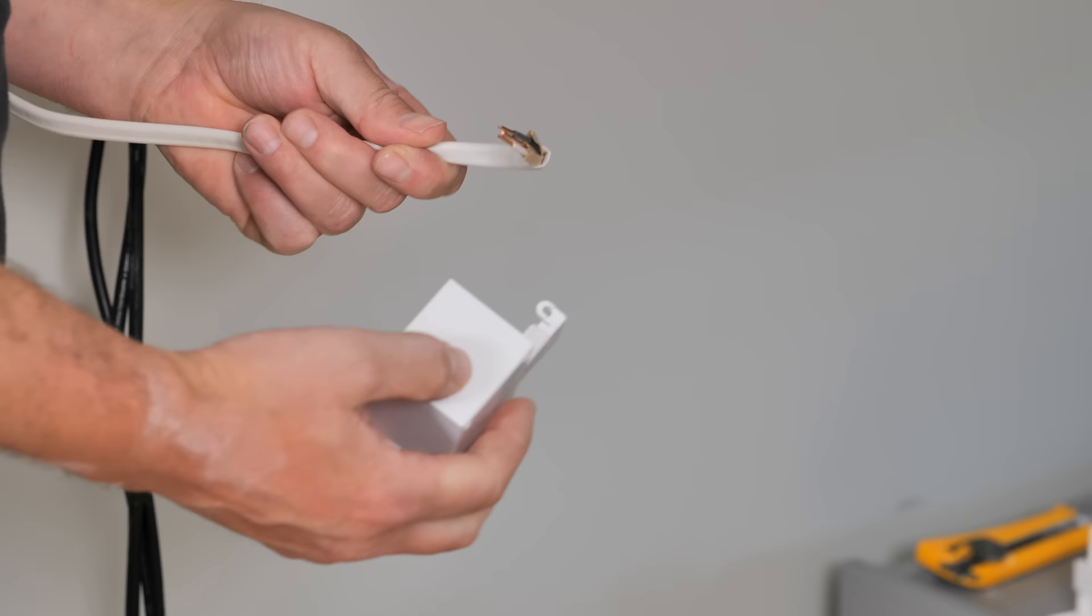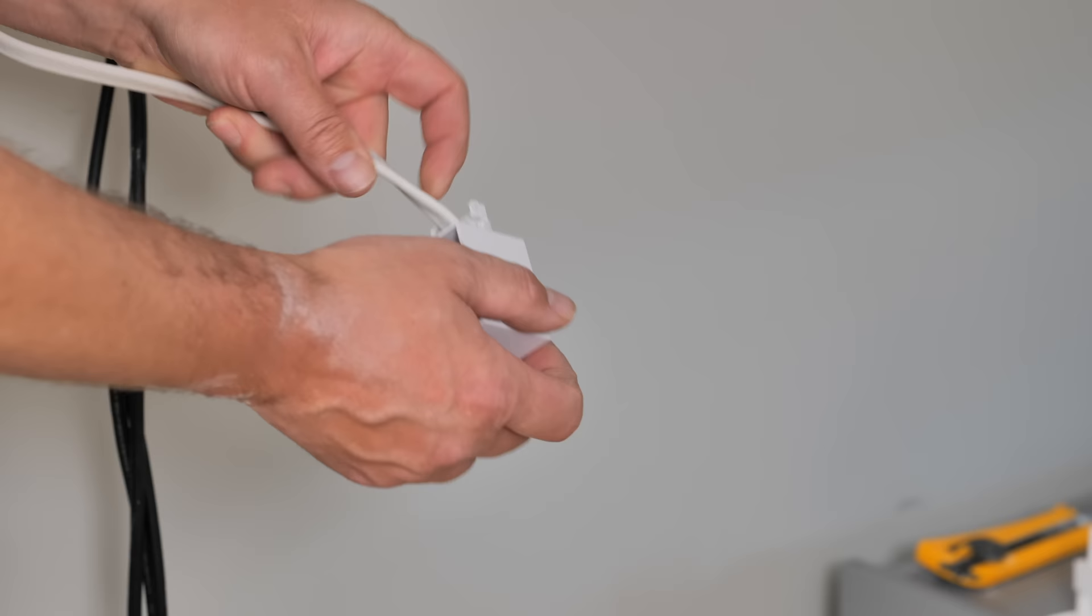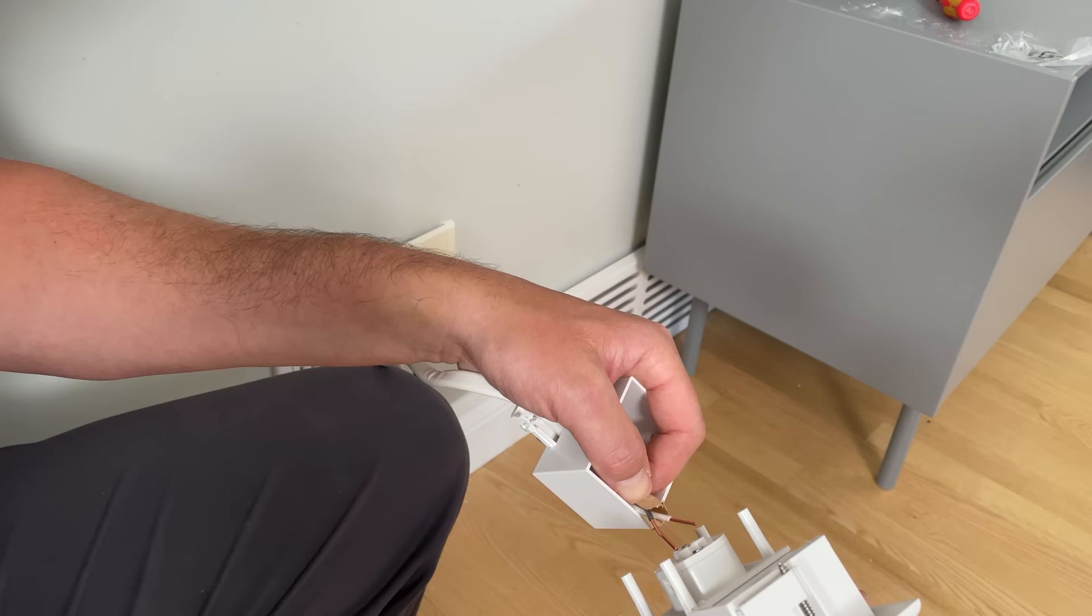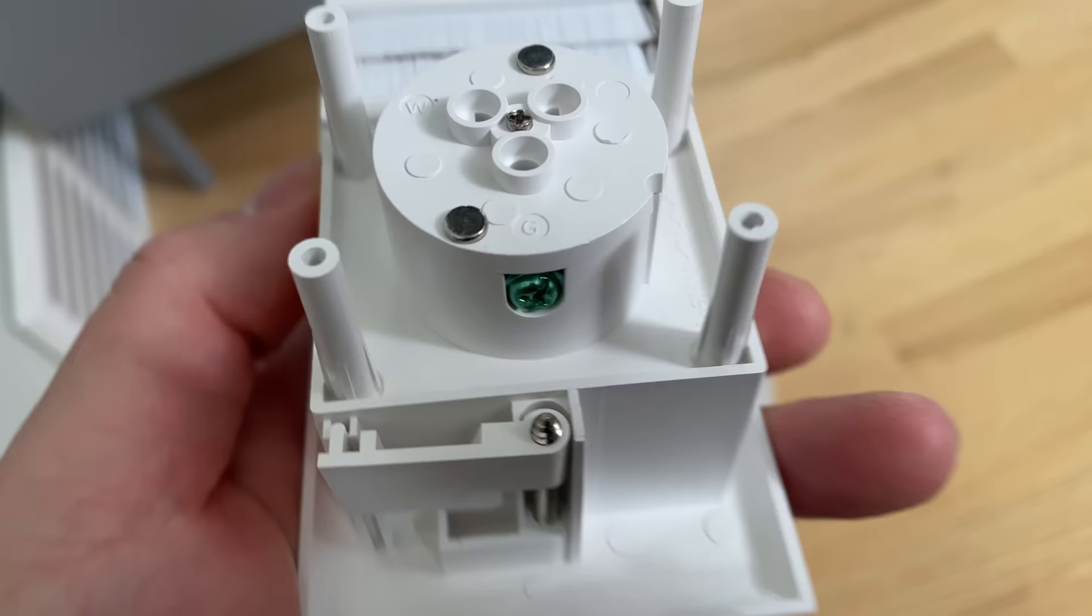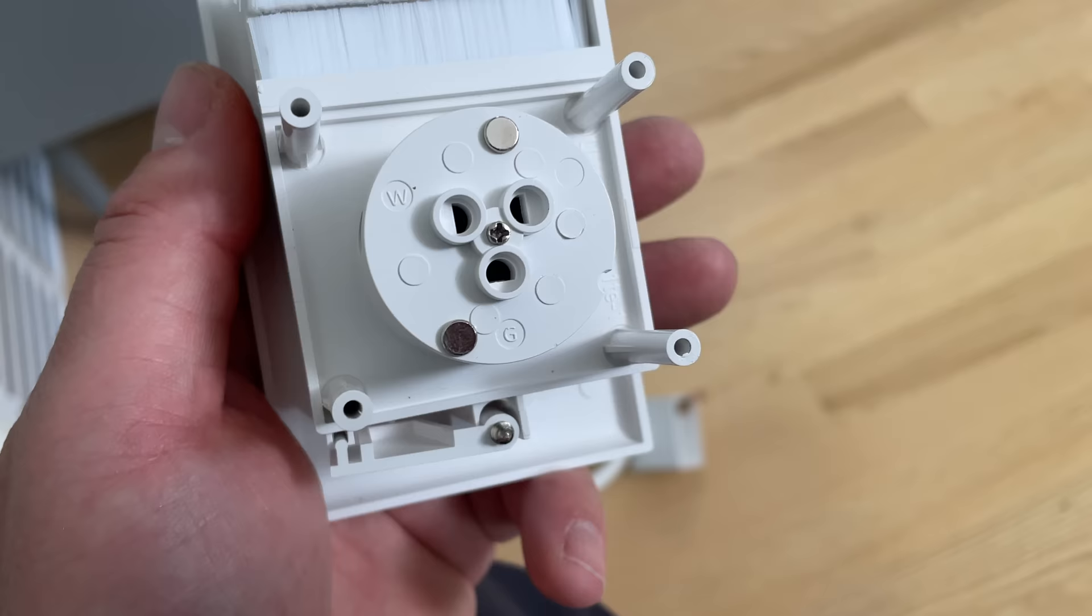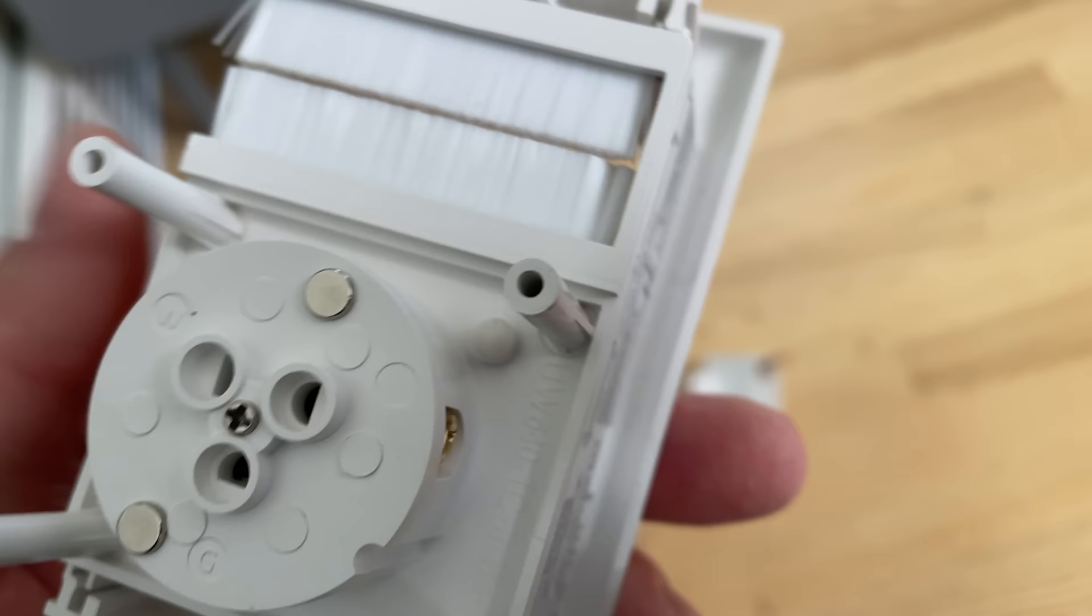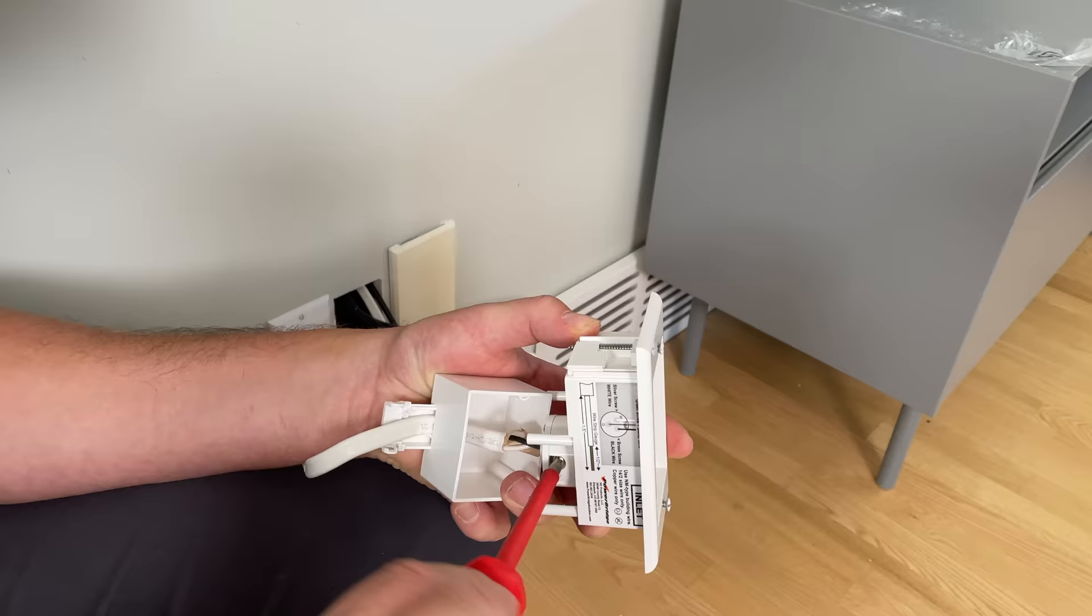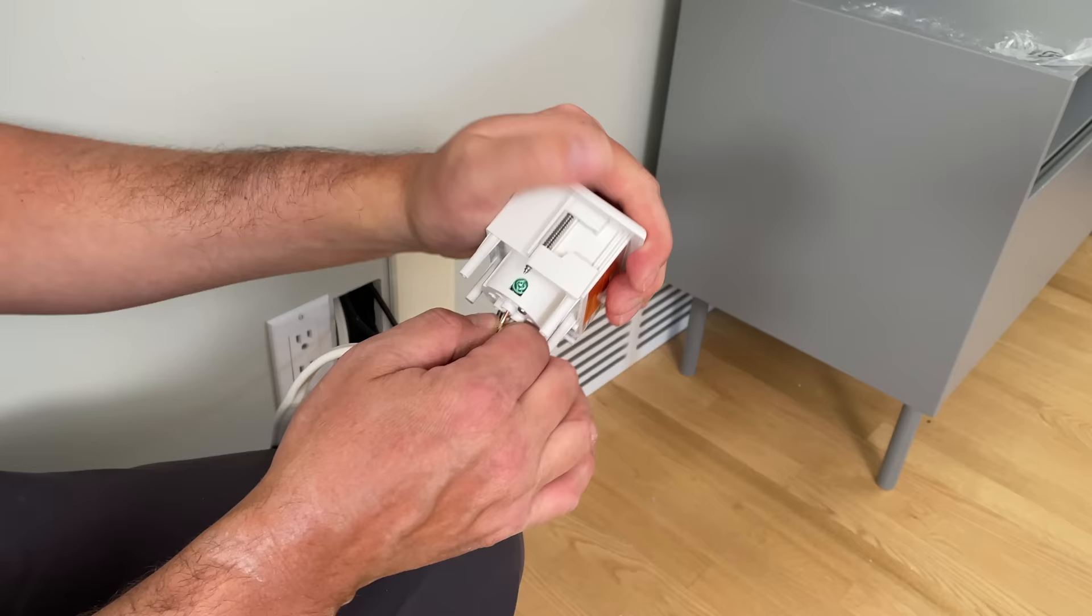To wire up the boxes, it's the same for both the top and the bottom box. The first thing you want to do is throw on the shield box, run the wires through there, and then you want to push them into the box connectors. I found it easiest to get the wires all kind of oriented in the way that you can push them all in at the same time. The ground, the bare copper wire is going to go into the green screw area. The white wire is going to go into the silver screw, and the black or the red, the hot wire, is going to go into the brass colored screw. Push those all in at the same time. Then you want to tighten up the connections with a Phillips screwdriver or a flat screwdriver. Tighten those nuts and screws nice and tight. Give the wire a tug just to make sure that it is connected and it's not going to pull out.